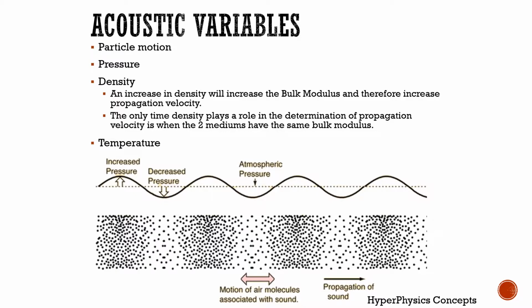Pressure is the concentration of force. Pressure increases during compression and decreases during rarefaction. Density is the mass divided by the volume. Different mediums have different densities, which will also affect the propagation velocity of sound waves. With a decrease in volume during compression, there is an increase in density. During rarefaction, there is an increase in volume, which results in a decrease in density. A higher density material tends to have a lower propagation velocity, and lower density material has a faster propagation velocity.